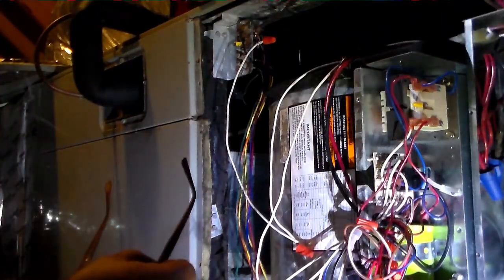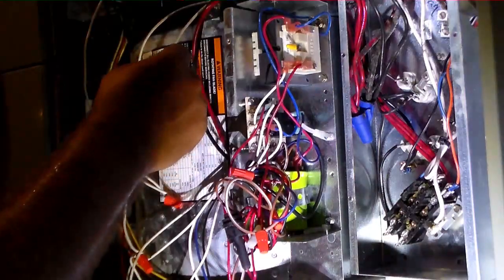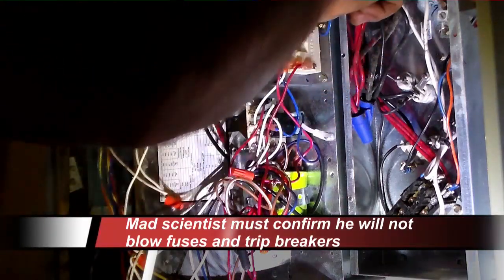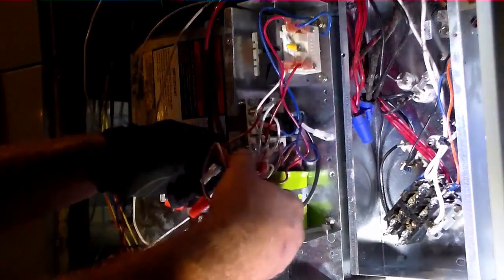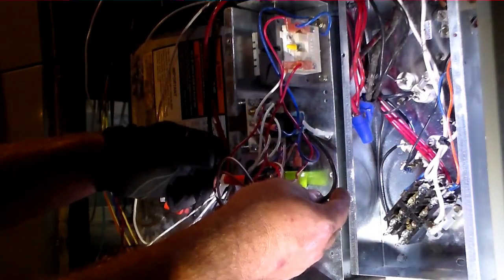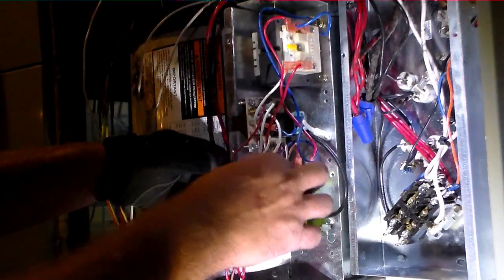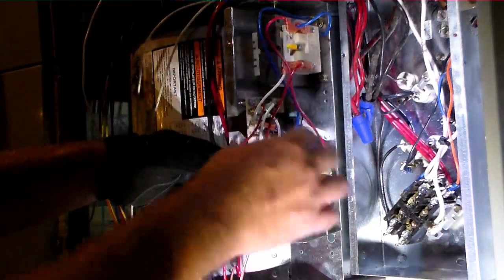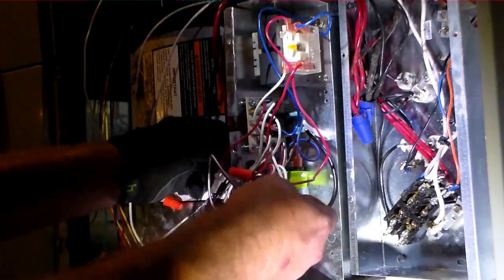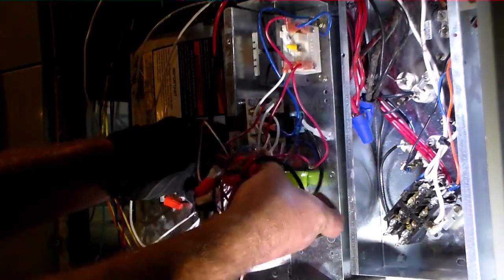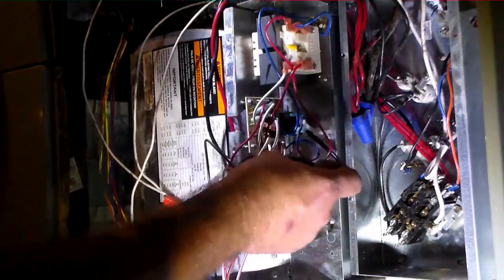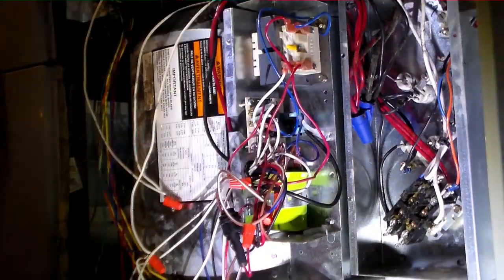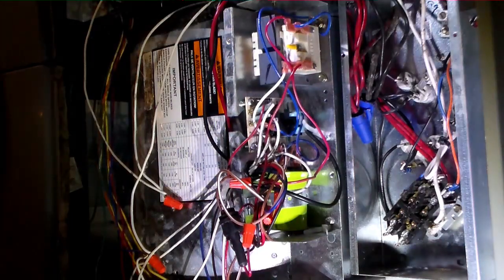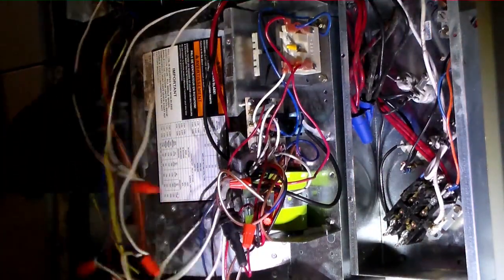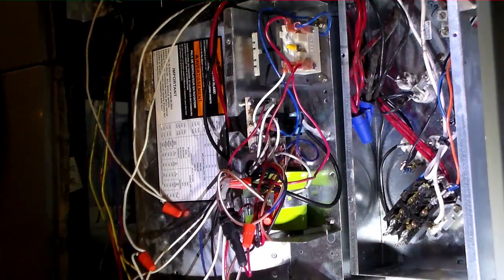So let's check through and see if we got everything. Alright, we got our transformer hooked up. High voltage comes in, goes out through here, comes around, goes to the fan control, goes to the transformer. Good. The other leg goes to the transformer, and then in turn goes directly to the fan. We have two wires not used, which are our other speeds. We have a whole dangling mess here, which we will put together.